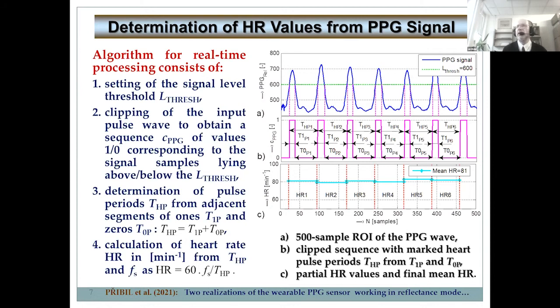The PPG signal can be used to determine the heart rate values. The algorithm used for the real-time processing must be fast, simple, but robust and stable. Our algorithm works in 4 steps. First, the threshold level is determined from the PPG signal. Secondly, the binary clipping is applied on the pulse wave. In the third step, the pulse periods, THP, are determined. And finally, the HR values are calculated. This process is demonstrated by a graphical example on the right.